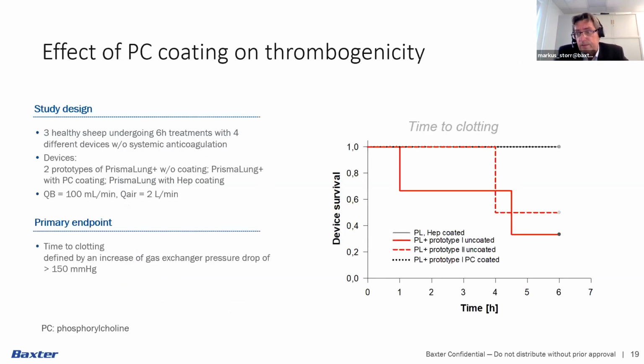Finally, we've tested the effectiveness of the antithrombogenic membrane coating. I mentioned that we use phosphorylcholine as a coating to reduce blood clotting. Therefore, 3 healthy sheep underwent 6-hour treatments without any systemic anticoagulation. Each sheep was treated with 4 different devices, 2 devices with coated membranes and 2 devices with non-coated membranes. On the right, this time to clotting analysis shows that both coated devices, one coated with phosphorylcholine, the other coated with heparin, showed no sign of clotting over the 6-hour treatment, whereas the non-coated devices showed premature clotting before reaching the 6-hour treatment time for the majority of the treatments.